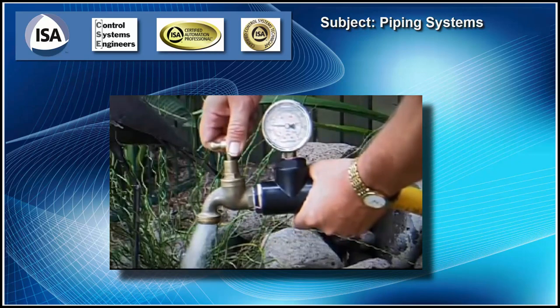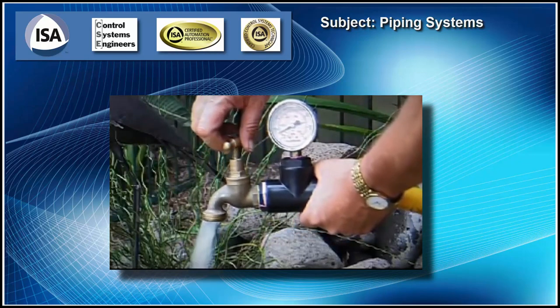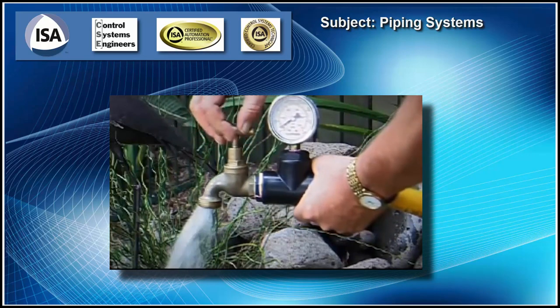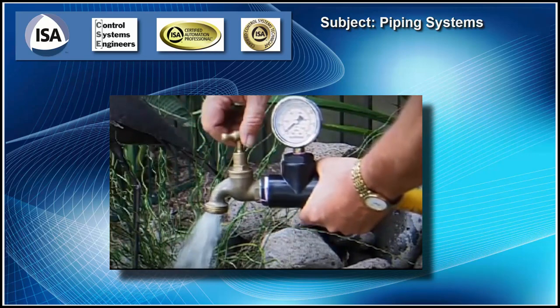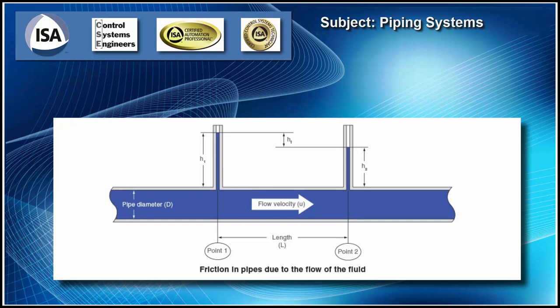As we carry this water through there, it has to do work to overcome the resistance of the pipe. This pipe is a big resistor, so it has to give up energy as it goes down the pipe. And as it goes down the pipe, we're constantly giving up energy and giving up energy, but mass in equals mass out, so we maintain our flow rate. Later on when we're doing our pump calculations, we'll see that in this piping system, the faster the fluid flows, the more resistance it offers. And this is due to the kinetic energy loss and the viscosity of the fluid.